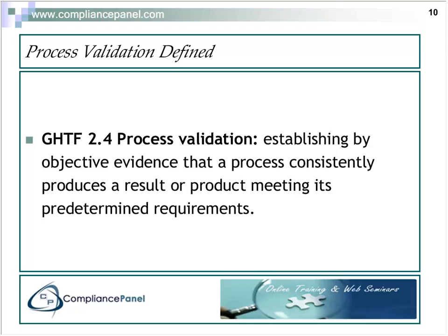The old saying is, if you didn't document it, you didn't do it. So we must provide some documentation that, first of all, we established a protocol, and second of all, that we successfully executed that protocol. And we're going to demonstrate that our process that we have created to produce this product consistently produces a result or a product meeting its predetermined requirements.